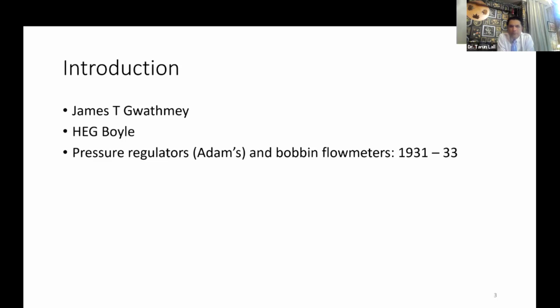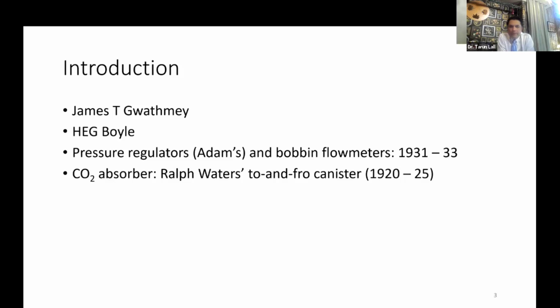And at the same time, a lot of work was being done on using low flow gases. So the first step towards that was probably Ralph Waters' to and fro canister. He showed that if carbon dioxide could be absorbed from the exhaled gases, then the exhaled gases could be reused. Then the circle absorber, which you can say was the forerunner of what we use today, was introduced by Brian Sword in 1928. And now successful administration of low flow anesthesia required precise delivery of gases at low flow, for which these bobbin flow meters were not good.